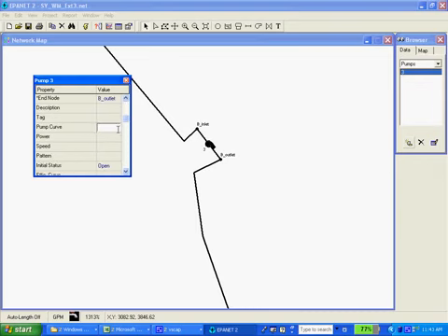Here's the pump curve, which I'll go ahead and enter in my next step. Notice there is a section here for a pattern to be entered for the pump. Be careful of that. I've accidentally put a pattern in for a pump, and it can cause a lot of problems unless you intend it to be there. For instance, if you put a community peak flow pattern in there unintentionally, you can end up with some really bizarre results on your model.